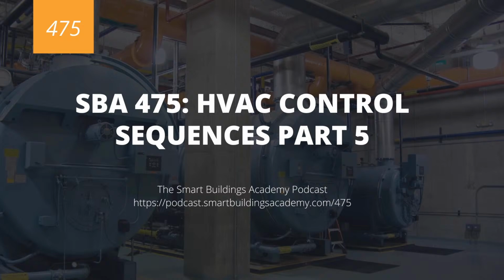It just depends on how your building profile is, how the loads affect, and how much heat loss you're going to have in the building envelope itself. There's a variety of variables that you need to take into account. But as I mentioned, there's really two ways we're going to do that, and that's either through supply temperature reset or mixing valve reset. So we're going to look at those two. I think we'll look at them in the sequence. If we don't, I'll come back to it.